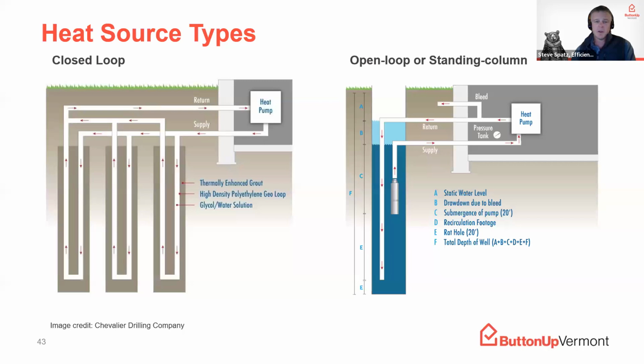A closed loop system is essentially that. It's a closed system where you're drilling a number of wells to a certain depth, depending on what the load needs to be for the home. And then you're running a loop of piping into those wells. So you're putting plastic pipe down into these wells that is one continuous loop from the heat pump back to the heat pump. And you fill that tubing with a glycol and water mix, and it stays closed off from the outdoor environment. You're cycling that water and glycol loop through the ground as your heat sink and heat source. An open loop system is the same process of drilling a well, but you're just moving water into and out of that well through the heat pump and exchanging the heat energy that way.